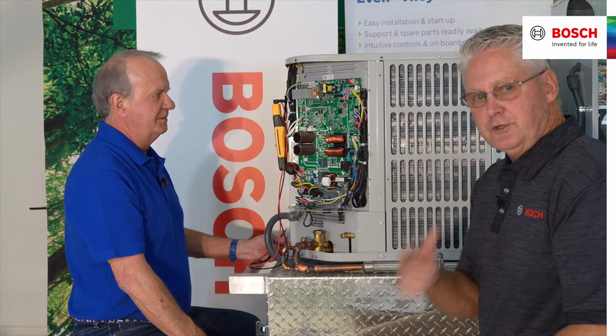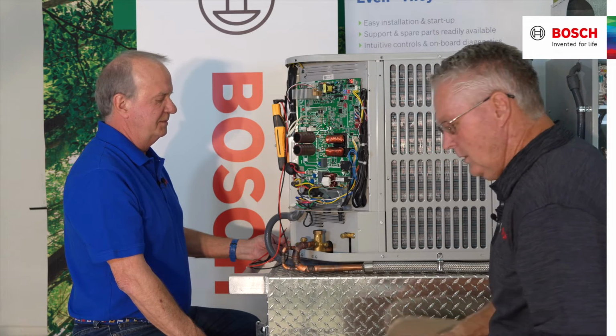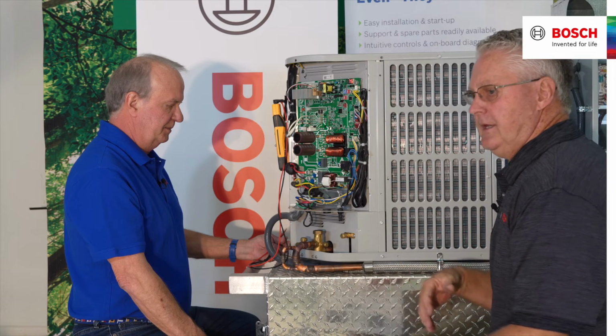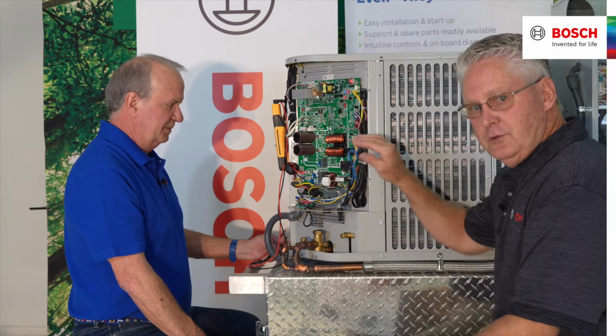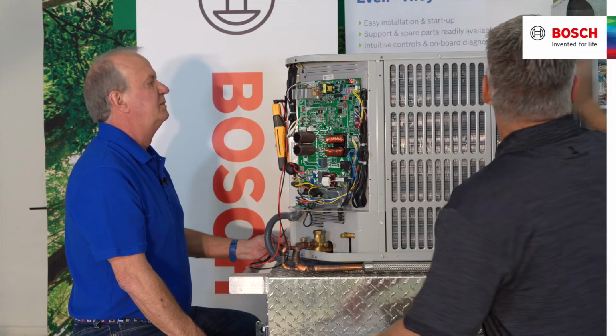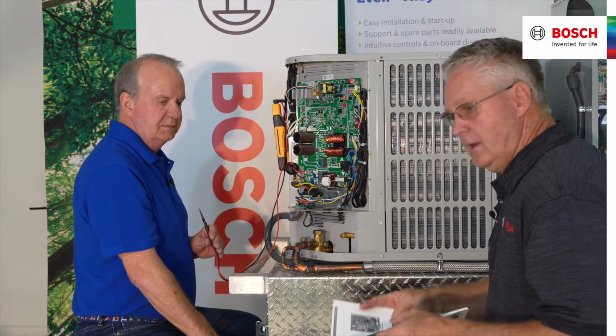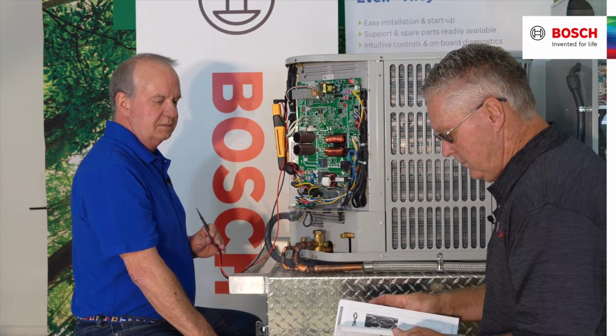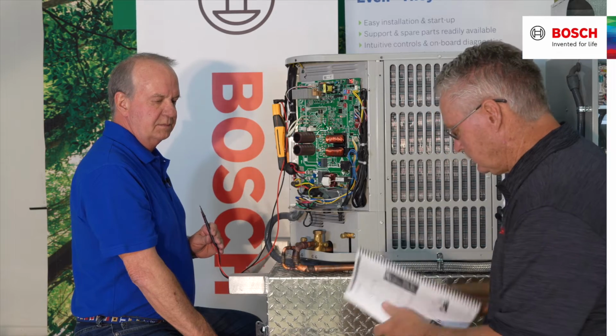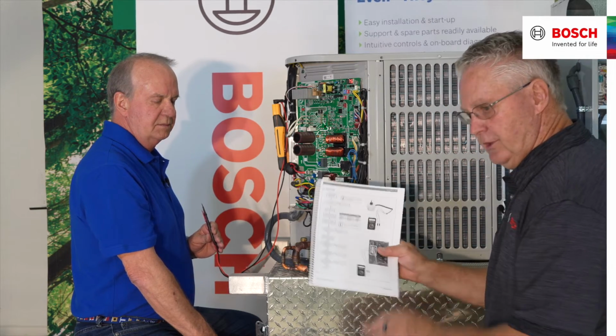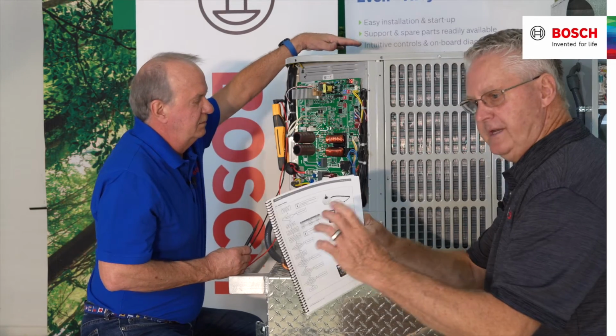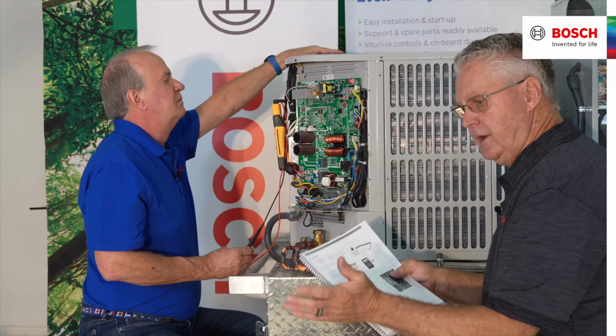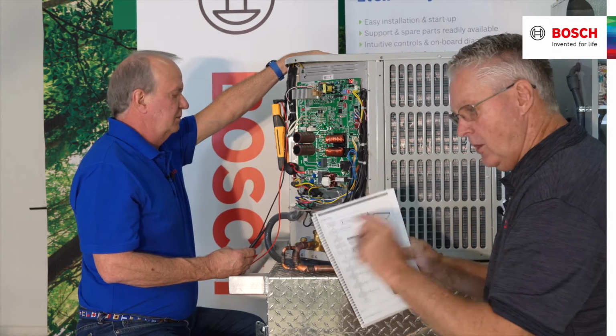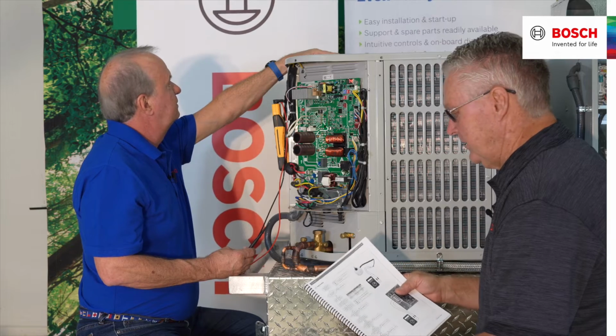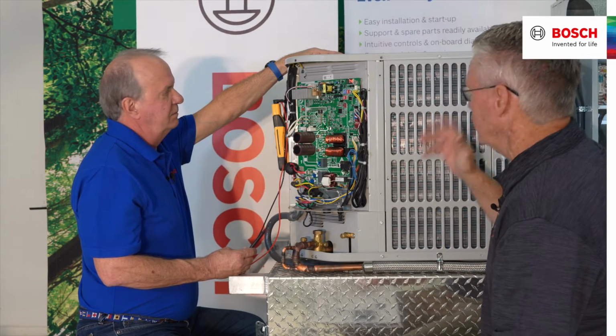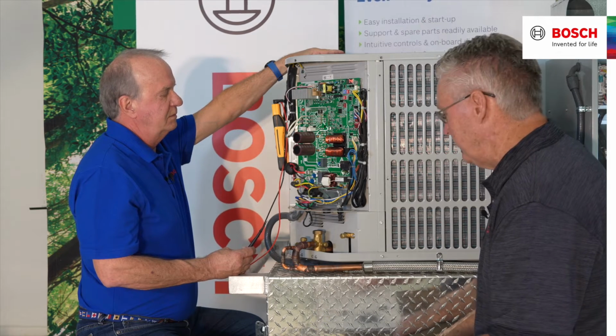And what we're going to do now is actually turn it on. We're going to see what the voltage coming through to the condenser fan motor will be. I'm getting these numbers from the service manual. The service manual is a really good depiction of the component itself, what is going to the motor, and what it's ohming out to if we take the plug away and ohm out the motor. We're looking at that. We're going to make a little bit of noise. We're going to move some air when this unit comes on.